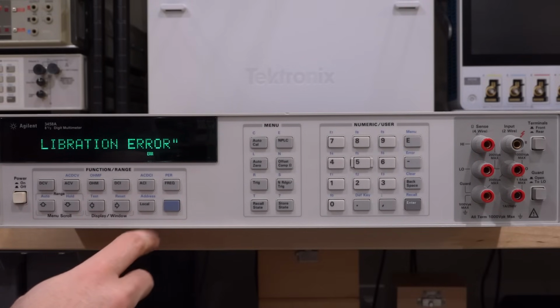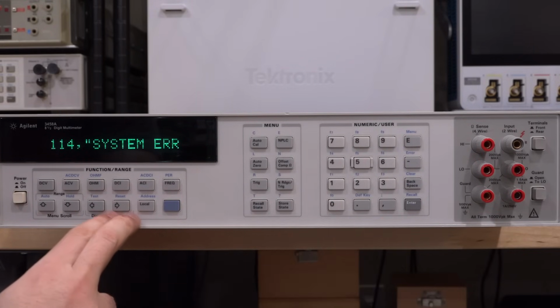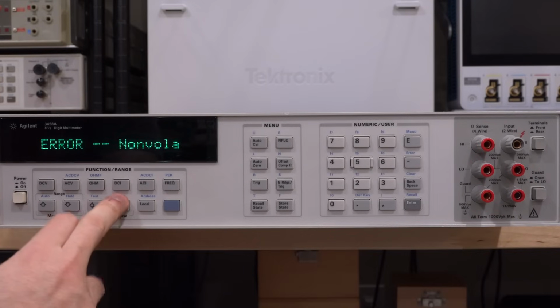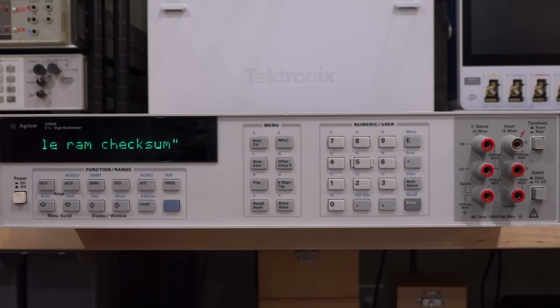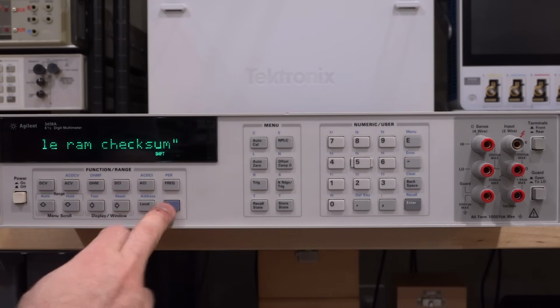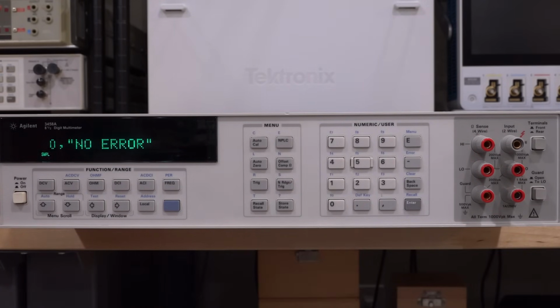Calibration error. Okay, anything else? System error. Oh, non-volatile RAM checksum. Okay, so that means that the battery on the unit has also run out. So there's multiple problems in here. There you go, all the errors are gone. So I think we should fix that battery problem for sure, because otherwise we're going to run into other issues. But the problem with the internal measurement, that's a bigger problem.